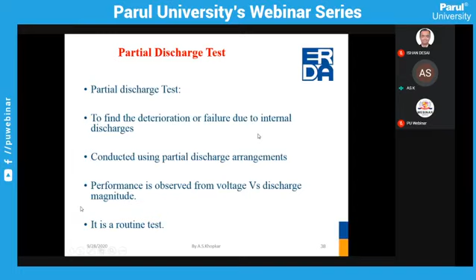For the basic requirement of the PD test, we require a Faraday cage. Faraday cage means a shielded room is required, because the PD test is a very sensitive test, and if there is external noise, that can also disturb our measurement. That's why we require the Faraday cage, or in other words a shielding room, so that external noise can be suppressed. We also require a PD-free source, meaning it should not have partial discharge of more than 2 pC. Electrical partial discharge is measured in picocoulombs, and the sensitivity of the circuit we use should be less than 5 picocoulomb, meaning we should be able to measure even below 5 picocoulomb.